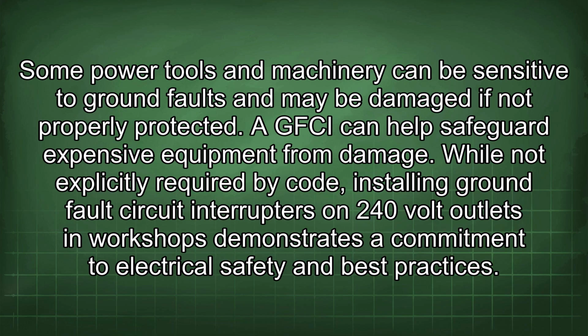Some power tools and machinery can be sensitive to ground faults and may be damaged if not properly protected. A GFCI can help safeguard expensive equipment from damage. While not explicitly required by code, installing ground fault circuit interrupters on 240-volt outlets in workshops demonstrates a commitment to electrical safety and best practices.